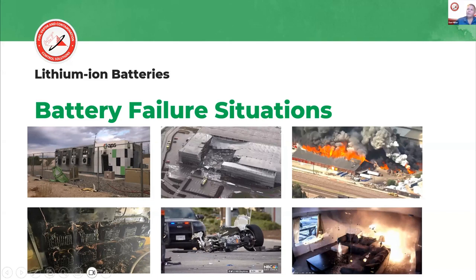The top left image is of a battery energy storage system in Surprise, Arizona, in 2019. They had a fire in that battery energy storage system. The fire department arrived and waited a significant period, at least a couple of hours, for the interior to cool down and resolve itself. Finally they approached carefully and opened the door. It ended up injuring three firefighters, one or two with career-ending injuries, because it backdrafted — the buildup of gases inside exploded as soon as it got the necessary air to make an explosive mixture.